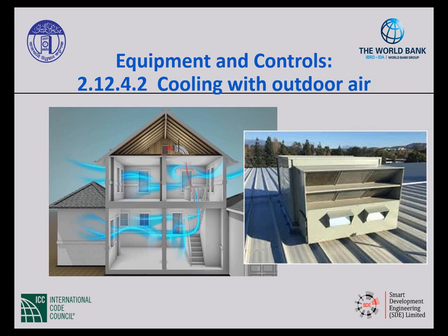A lot of people see it as an economizer, but there are other ways to do it. And so depending on what kind of mechanical system we have, what am I doing to use the outside air when it would be more efficient to do so? Now, there are some exceptions. Cooling with outdoor air is not required if the air handling system capacity is less than 2,500 liters per second, or the total cooling capacity is less than 40 kilowatts. Another exception is where the quality of outdoor air is poor, so that it would require too much treatment of the air. Maybe there's a fire outside, or maybe it's just a bad air quality day.